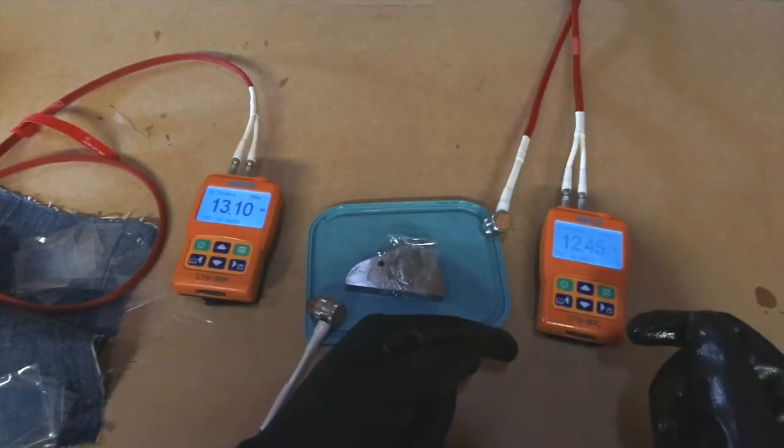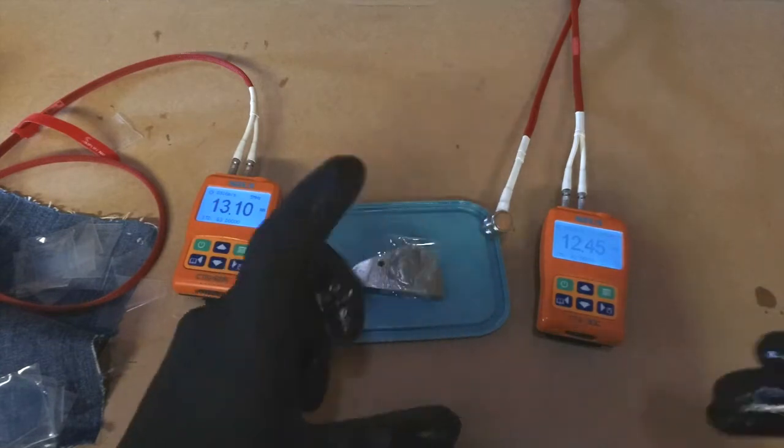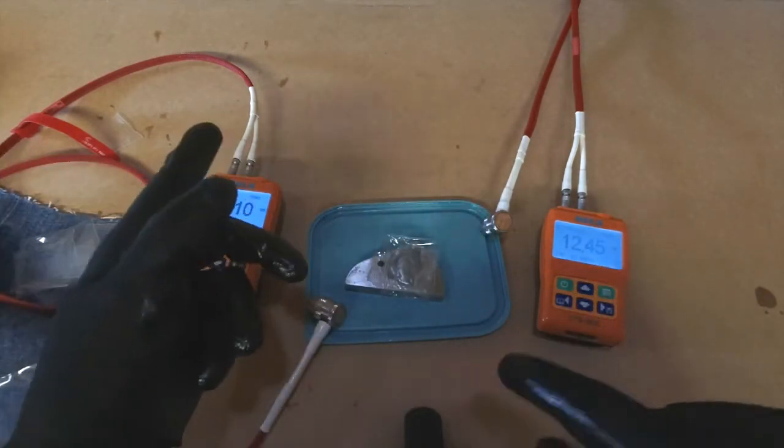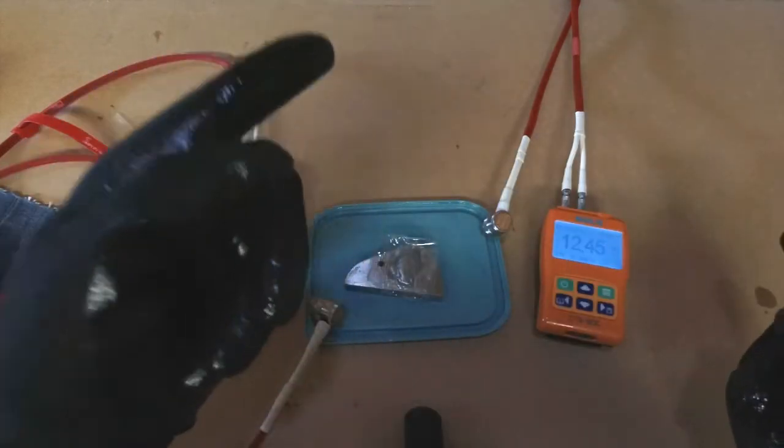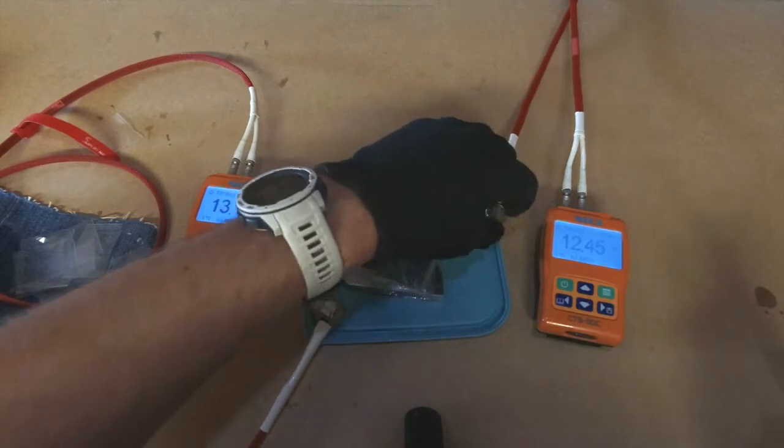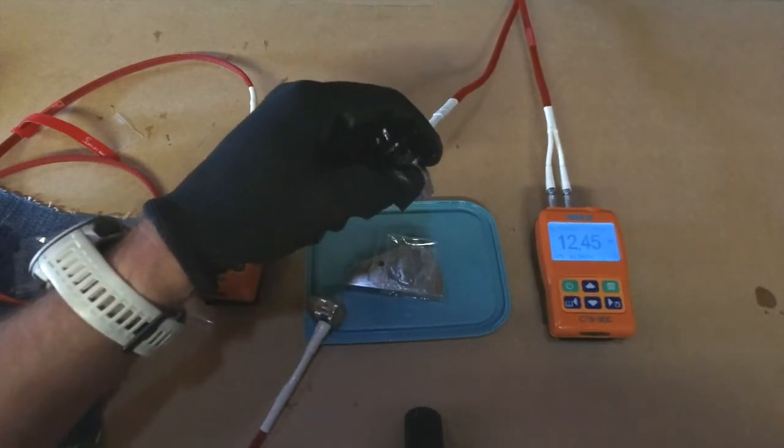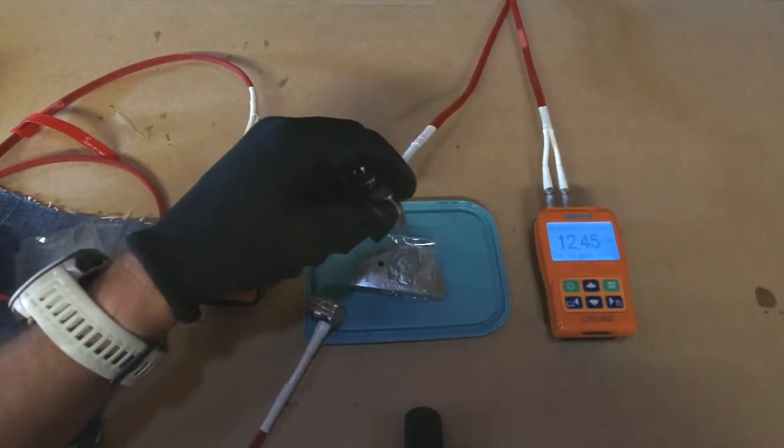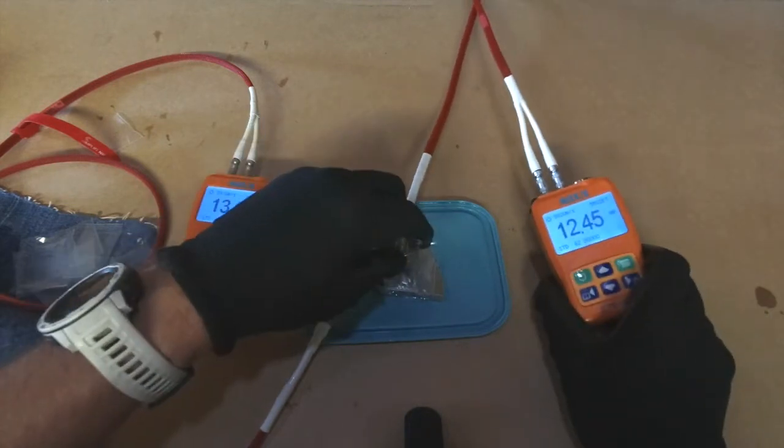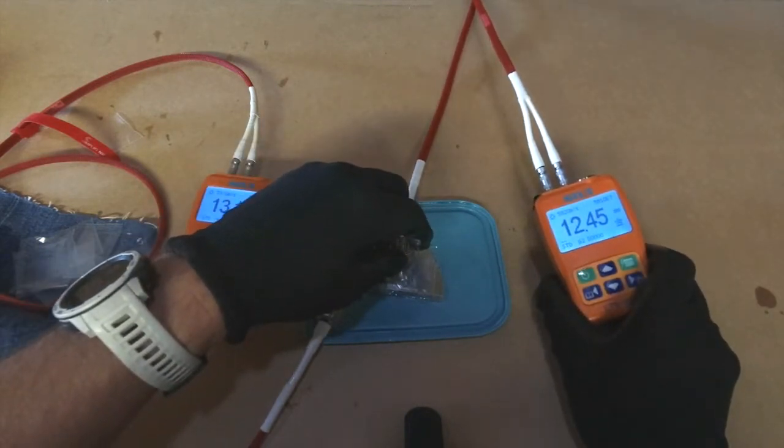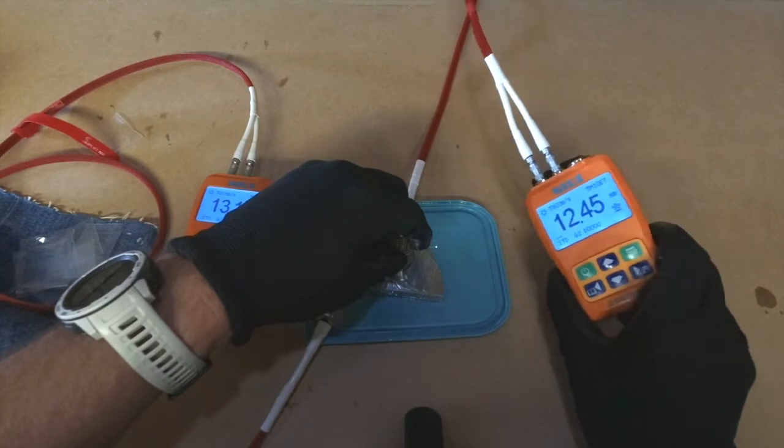This CTS-30C uses different logic. So it looks at the first, from the interface of the probe and the material through to the first echo, but it takes its readings from the first echo to the second echo. And what we should expect to see is almost no variation. No variation.